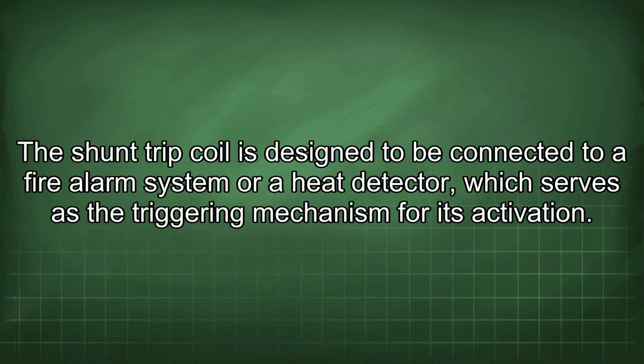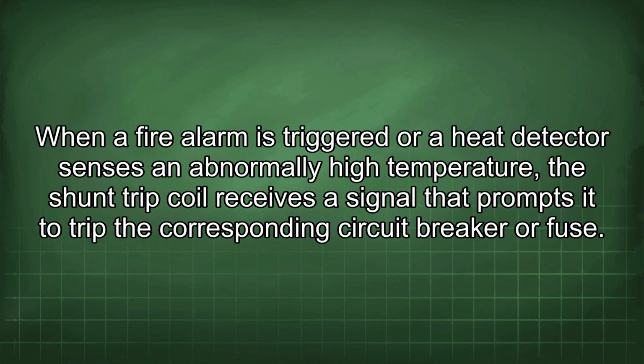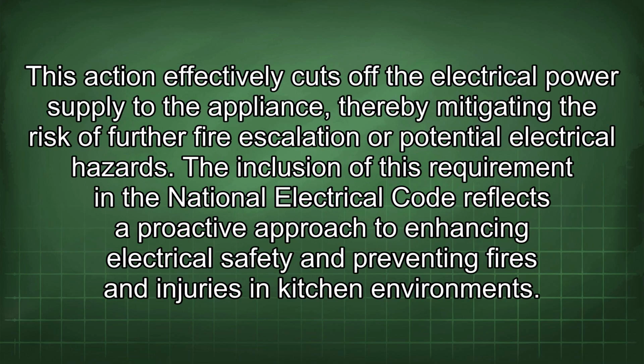The shunt trip coil is designed to be connected to a fire alarm system or a heat detector, which serves as the triggering mechanism for its activation. When a fire alarm is triggered or a heat detector senses an abnormally high temperature, the shunt trip coil receives a signal that prompts it to trip the corresponding circuit breaker or fuse.